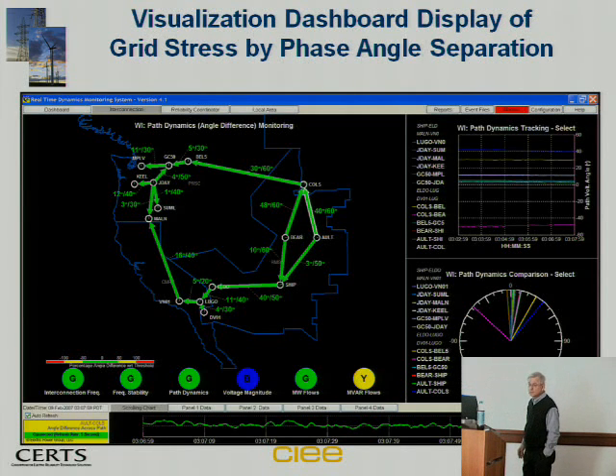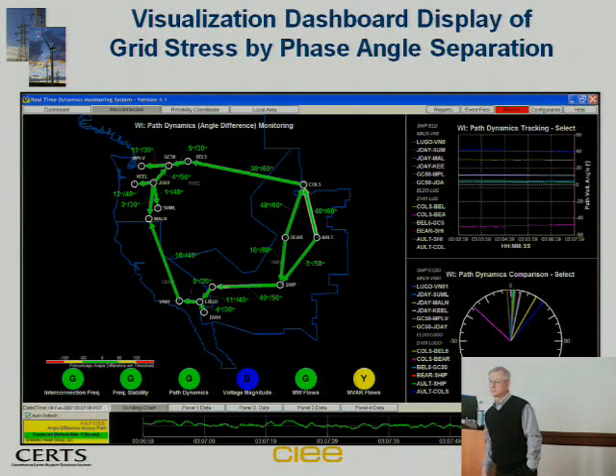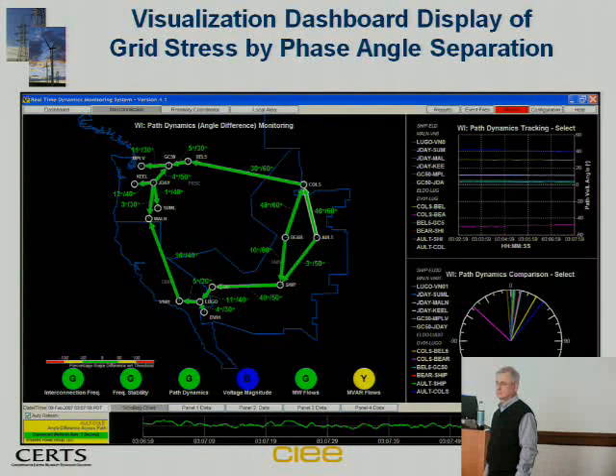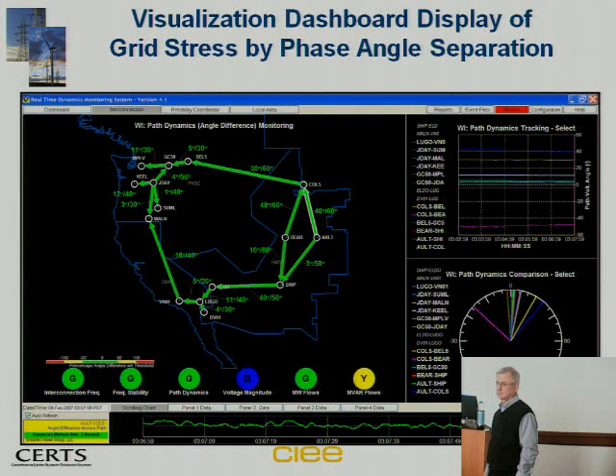The degrees are pretty close together, so you need the minutes reading, and then it gets — in other words, a fraction of a degree. And then presumably the phase shift translates into power flow in one direction or the other, right? Right, power flows from higher angle to lower angle. And how elastic is that — is it one minute? How do you convert a one minute shift into how many megawatts?